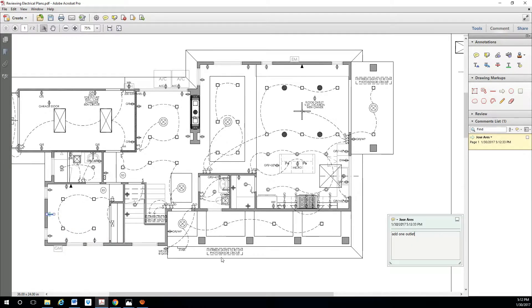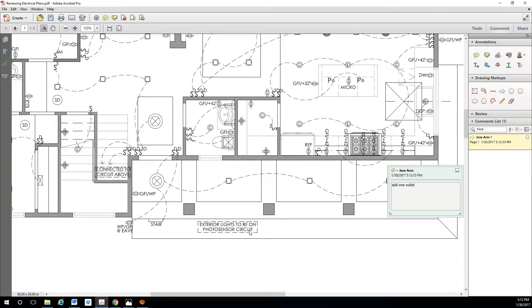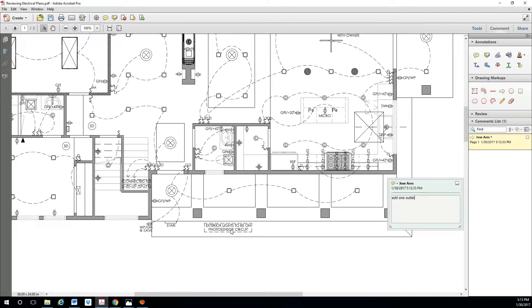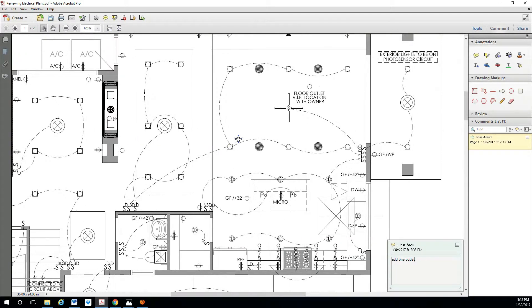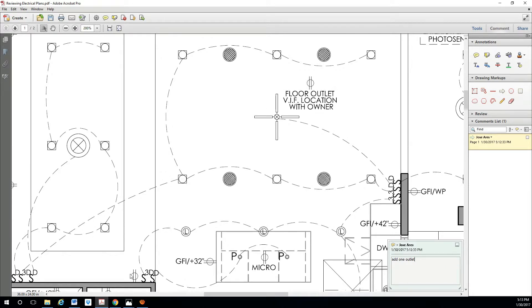You will also see other indications — for example, 'exterior lights to be on photosensor circuit.' This means that per code, all exterior lights must be on a photosensor circuit, where lights stay on during the night and turn off automatically when the sun rises. We will also show outlets for electric cars, and sometimes floor outlets — for example, in open spaces where it is useful to have connections for a seating area or lamps without running cables from the wall.